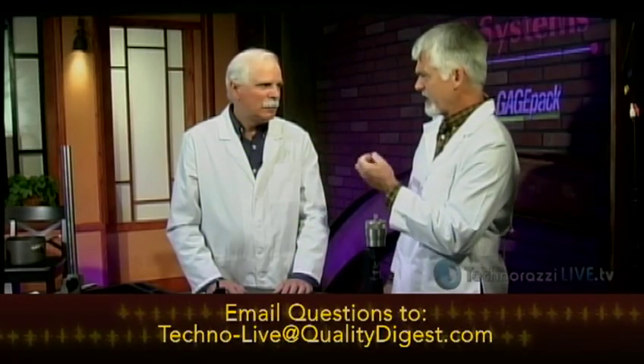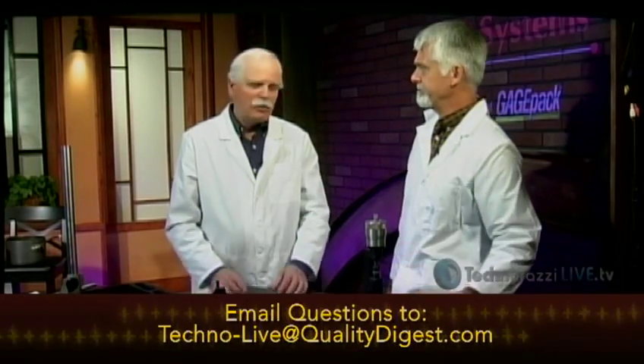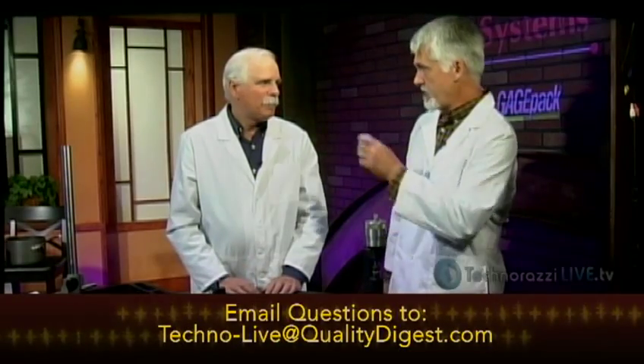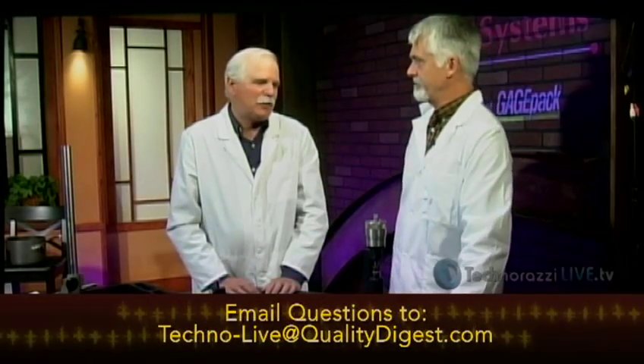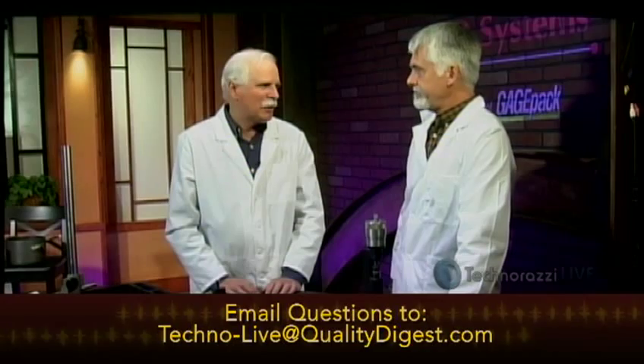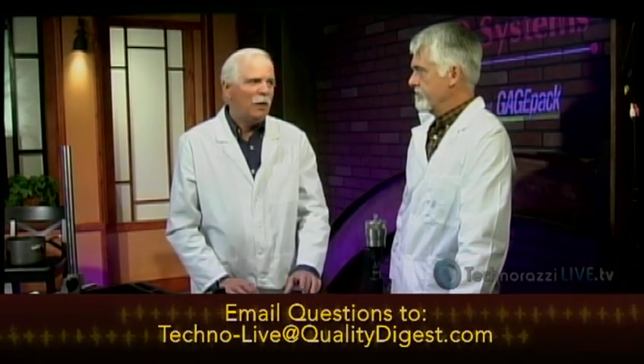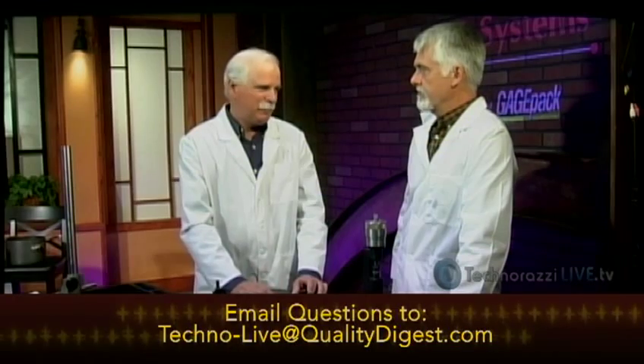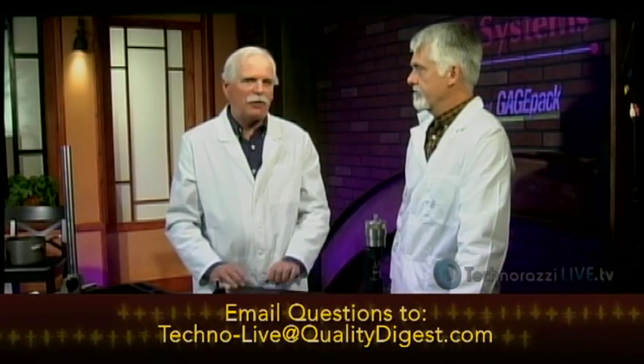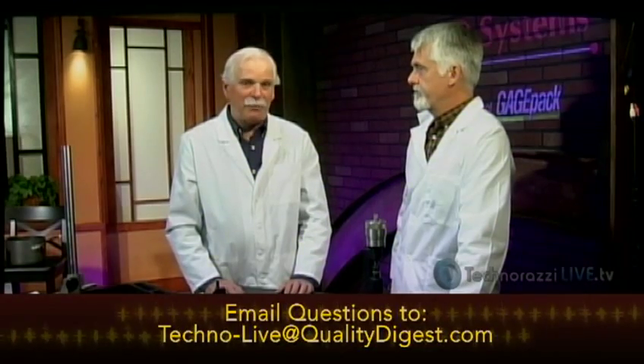Right. It's not usually scribed on the back or anything like that? No, the tips are too small. On the indicator itself, no, because there's no serial numbers, there's no model numbers on the contact points. Okay. Probably the tool crib, if they had more than one, they probably have a little stack, and they would say this is for the Mitutoyo 503-102. And they would use those till they ordered new. But just because it threads in does not mean it'll work.